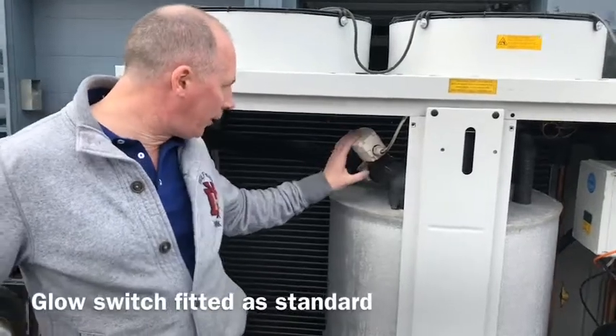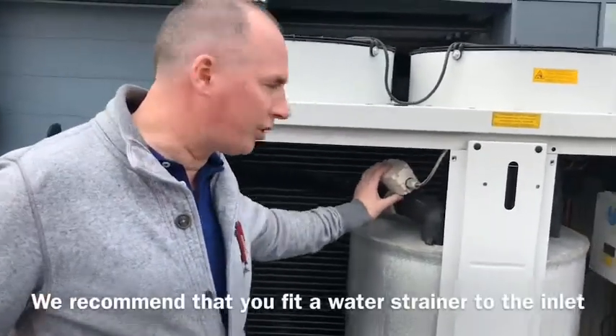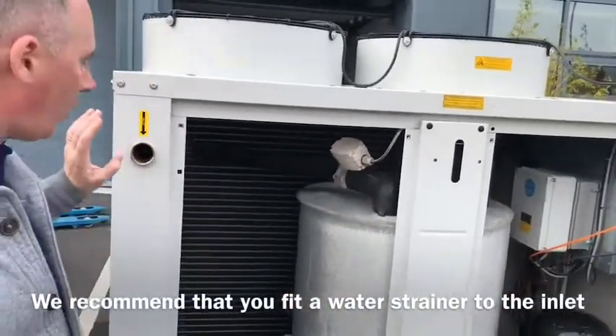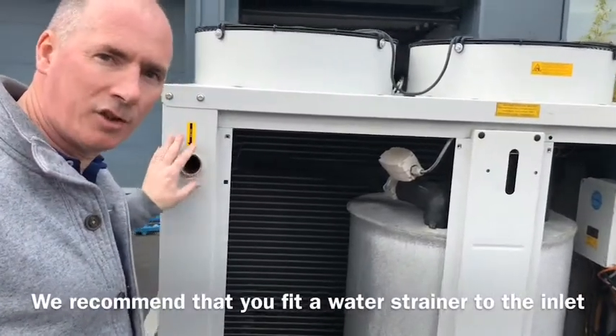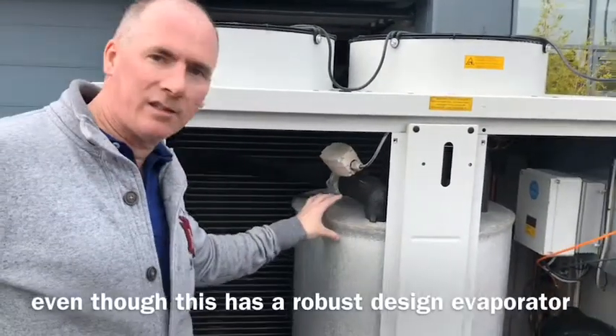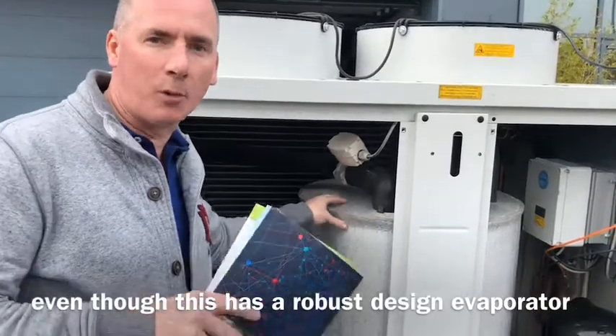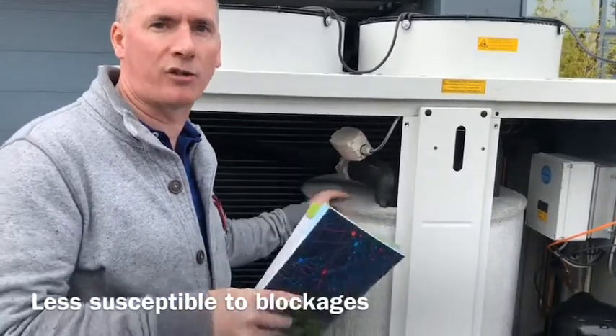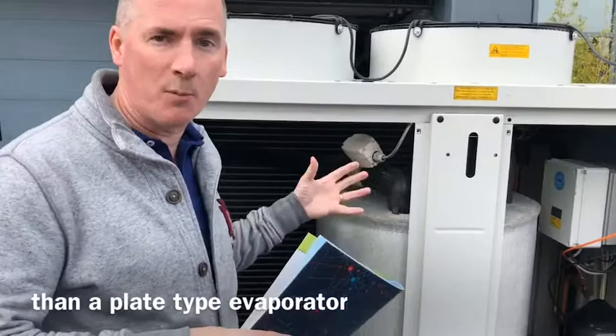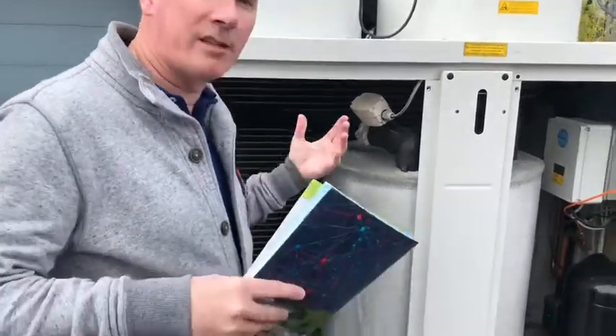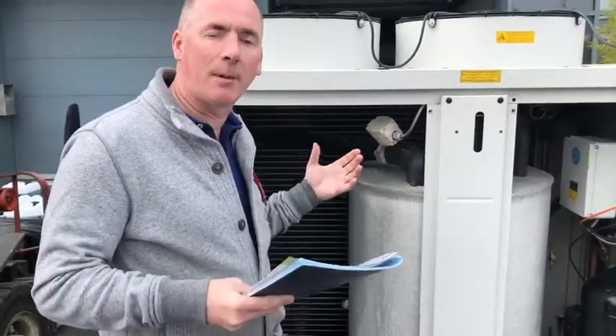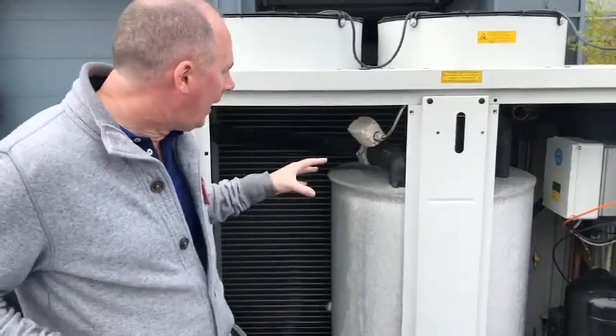They also come with a flow switch as standard, built within the chiller. We do recommend, by the way, that you always put a water strainer on the inlet to the chiller to protect it. Even though this design of evaporator is a much more robust design, and they're a lot less susceptible to blockages or dirt than a plate type evaporator, which would be much more common in the industry. But like I said, they're primarily designed or manufactured for aircon applications.